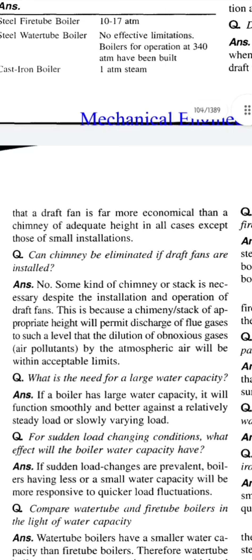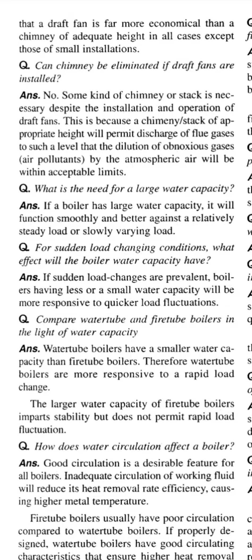Question: can the chimney be eliminated if draft fans are installed? Answer: no. Some kind of chimney or stack is necessary despite the installation and operation of draft fans. This is because a chimney stack of appropriate height will permit discharge of flue gases to such a level that the dilution of obnoxious gases, air pollutants, by the atmospheric air will be within acceptable limits.